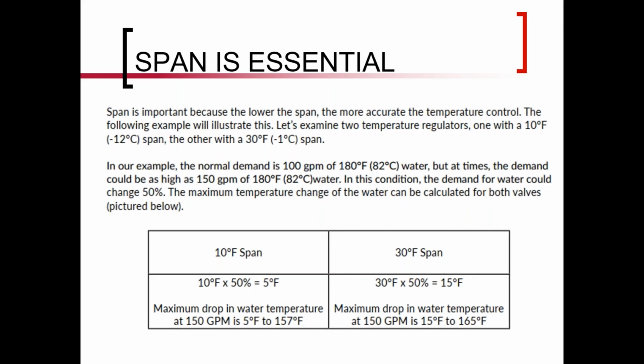But then the flow rate increases and the valve needs to compensate for that. So we're going to increase the flow to 150 GPM. Well, with a 10-degree span, that's a 50% increase in flow. It's going to be basically a 5-degree change. So in this case, the drop in water temperature that you might see for a little while, again, it's supposed to be 175. Whereas with a 30-degree span, that 50% increase is now 15 degrees F, so it goes down to 165.